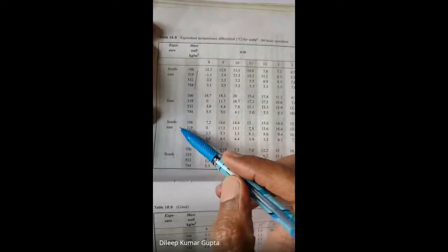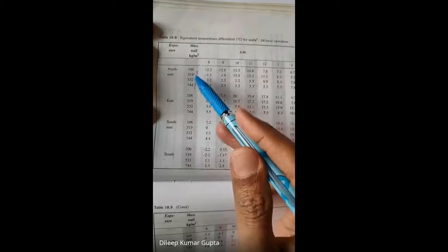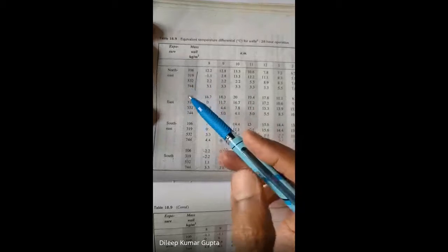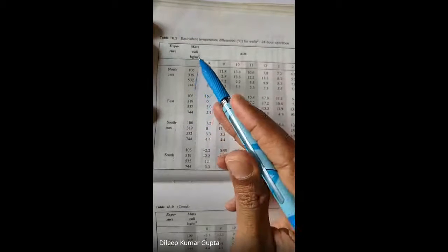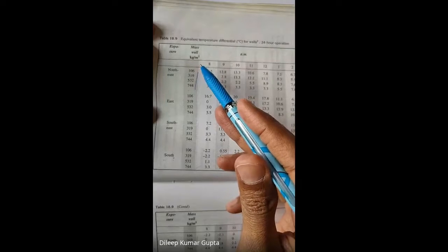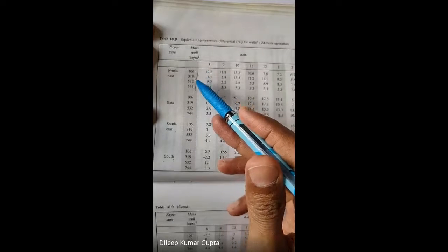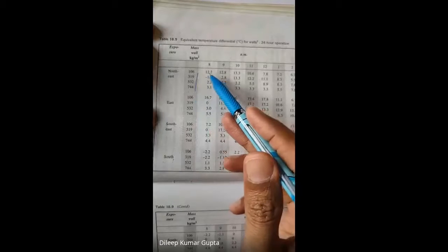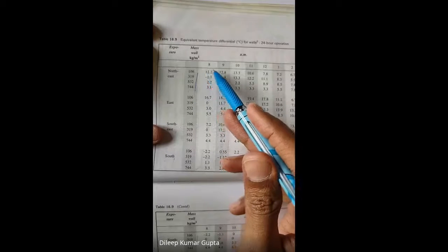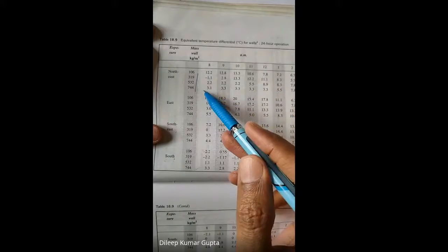So here the tables are given like this: north wall, east wall, each and every wall with respect to mass of wall per meter square based on the density, basically density multiplied by thickness. This is mass of wall per meter square. So density multiplied by thickness. So this will be mass of wall, and with respect to that, with respect to time, 9 o'clock morning to 8 o'clock evening. What is the temperature difference here? In 24 hours or 12 hours of operation.